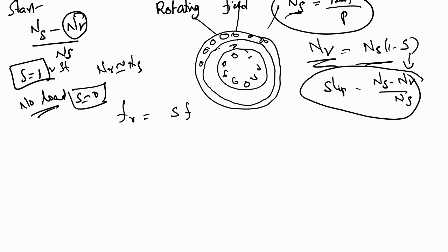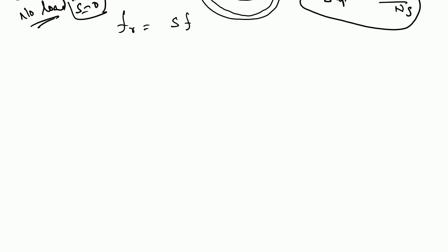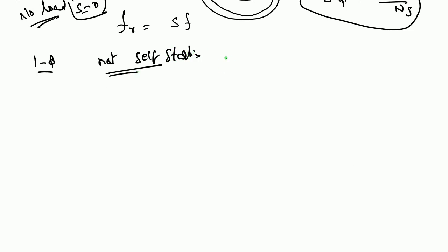The three-phase induction motor is self-starting. However, a single-phase induction motor is not a self-starting machine — this is very important. To make it self-starting, we split the winding into a main winding and an auxiliary winding with a phase difference of 90 degrees. Types include split-phase, capacitor start, and capacitor start-capacitor run motors.